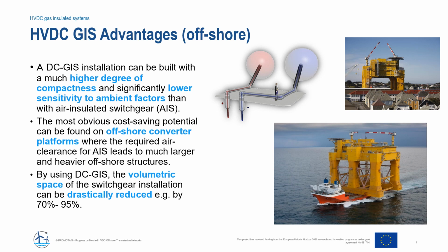The new compact generation of HVDC GIS installations can be built with a much higher degree of compactness and significantly lower sensitivity to ambient factors than air-insulated switchgear. The most obvious cost-saving potential can be found on offshore converter platforms, as shown here. Such converter stations are challenging during construction and installation. Some problems could be mitigated if the platform size could be reduced. By using HVDC GIS, the volumetric space of the switchgear installation itself can be reduced by 70 to 95%, which may result in a size reduction of 10% of the total platform.